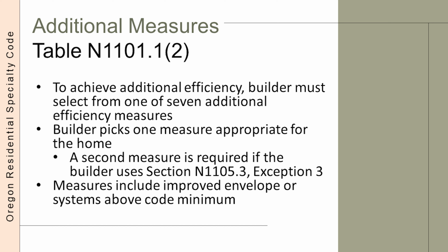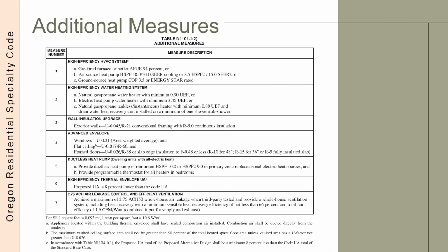We'll get into this exception later, but to put it simply, 2 additional measures are required for homes installing their ductwork outside of the thermal envelope. The measures range from equipment efficiency improvements to envelope enhancements, and even a combination of equipment and envelope. But because the measures are beyond the prescriptive requirements, it's important to know what measure is selected. So this is the additional measures table. The measures can include equipment upgrades.